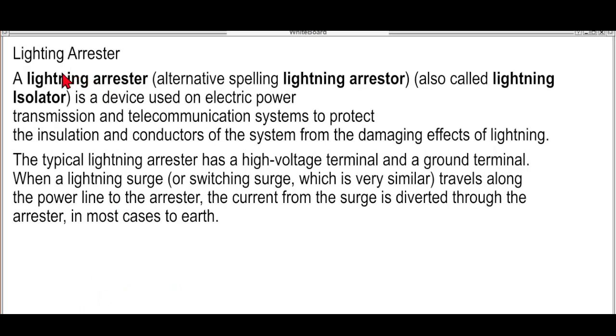Okay, then we have also lightning arrester, also known as arrestor. It is a device used in transmission and communication systems to protect the insulation and conductors of the system from the damaging effects of lightning. A typical lightning arrester has a high voltage terminal and a ground terminal. When a lightning surge hits our lightning arrester, it will go to the ground or the air.